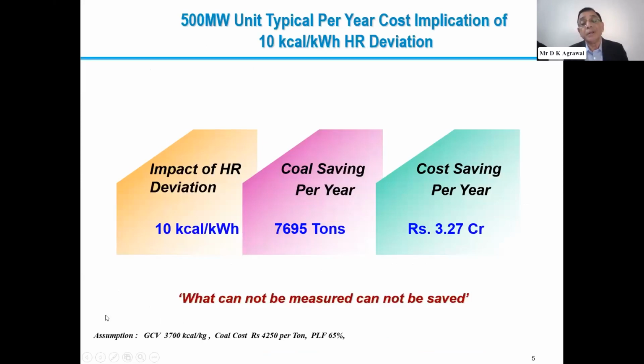Well, here, as has been indicated in the earlier presentation, this is a typical example for a 500 megawatt unit. A 10 kilocalorie impact on heat rate is going to be about 3.27 crores, and in terms of coal, it's 7,700 tons. And as I explained about the impact on CO2, you can multiply this coal by 1.2 to 1.25, and that is about 10,000 or so tons of emissions impact.